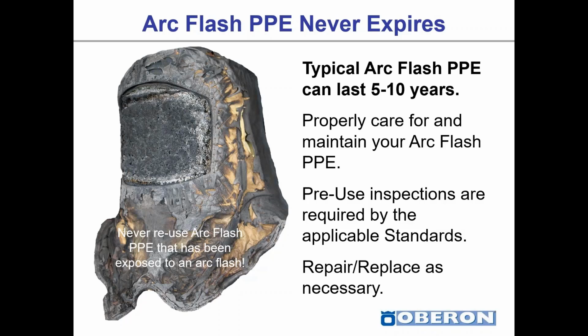Arc Flash PPE never expires. The typical Arc Flash PPE can last 5 to 10 years, often longer. So properly care for and maintain your Arc Flash PPE. Pre-use inspections are required by the applicable standards. Repair and replace as necessary.